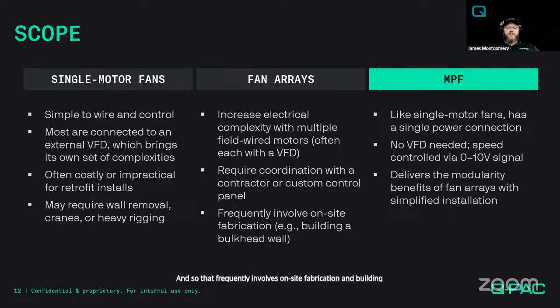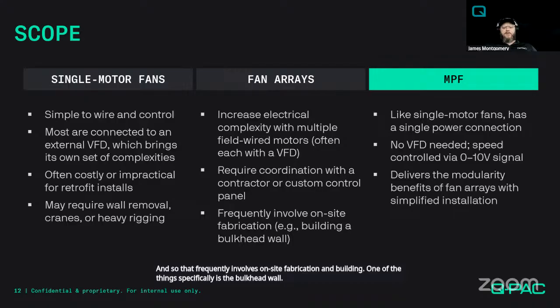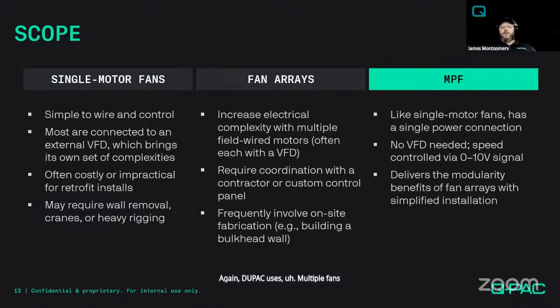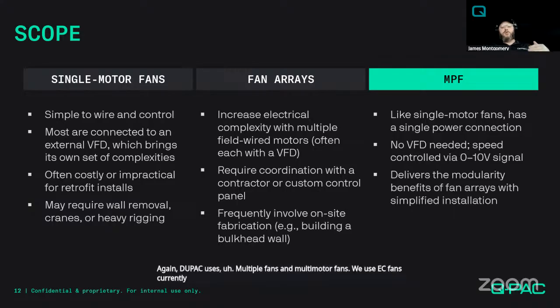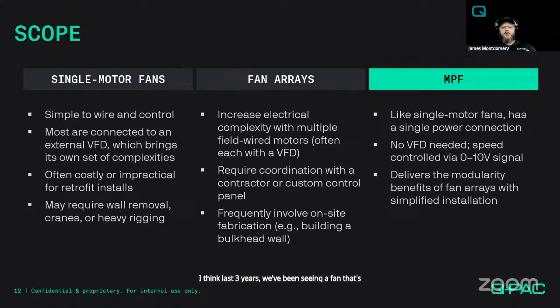One of the things specifically is the bulkhead wall. With the Q-PAC system, our fan frame, and I'll talk about that in a minute, is designed in such a way that it fits the existing area of the space and no bulkhead wall is required to be designed. Again, Q-PAC uses multiple fans and multi-motor fans. We use EC fans currently. There's always new technology coming around the corner. We were at AHR this past year, and I think for the last 3 years, we've been seeing a fan that's comprised of printed circuit cards. So no more coils, printed circuit cards. That's a pretty fancy thing. We could talk about that later.